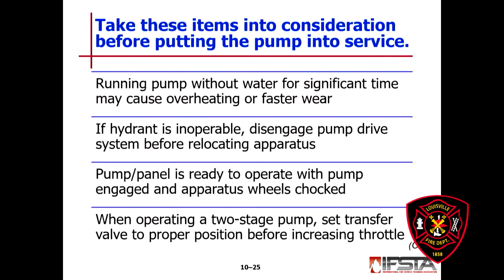Some of these things I've already talked about, but running your pump without water for a significant amount of time can cause overheating. For a few minutes it's okay, but if it goes several minutes—say we're having issues getting water—then open that tank-to-pump line and get water circulating through the pump. You're probably already doing that.